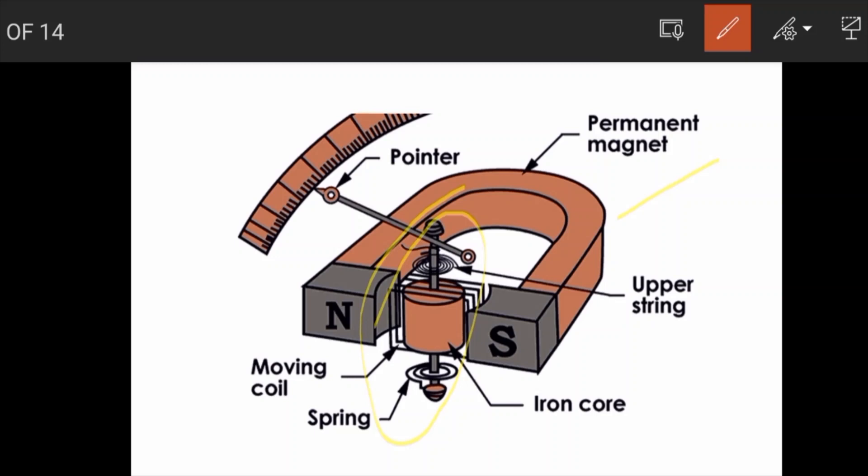The instrument uses an upper string and a lower string made of phosphor bronze. These phosphor bronze strings provide the controlling torque, and also serve as the incoming and outgoing leads of the current.